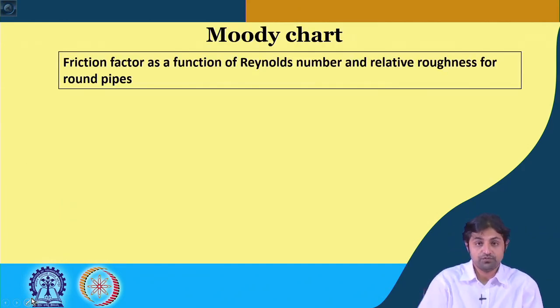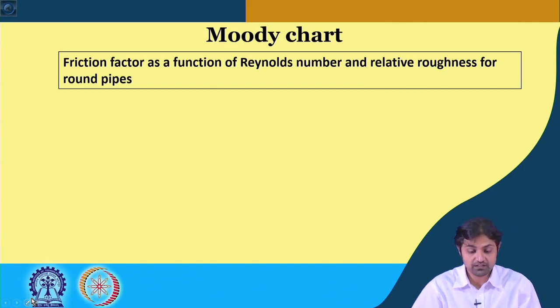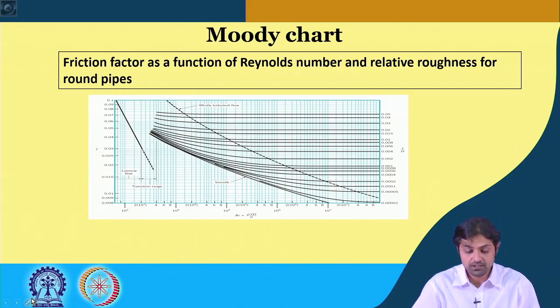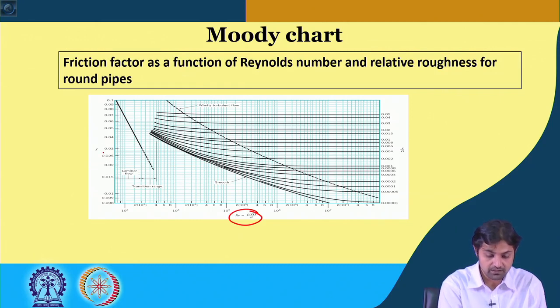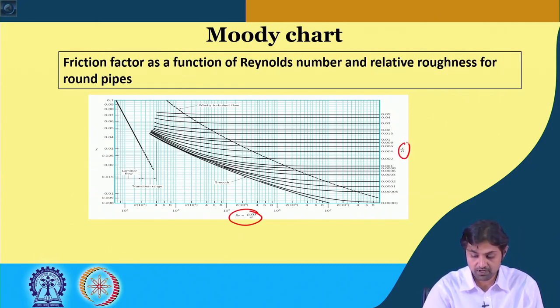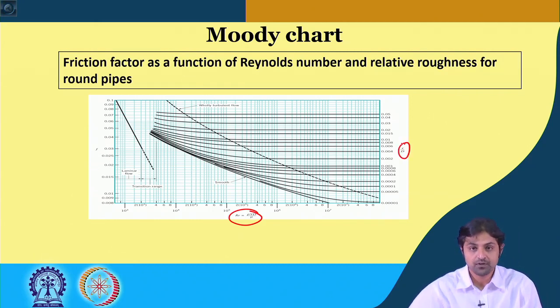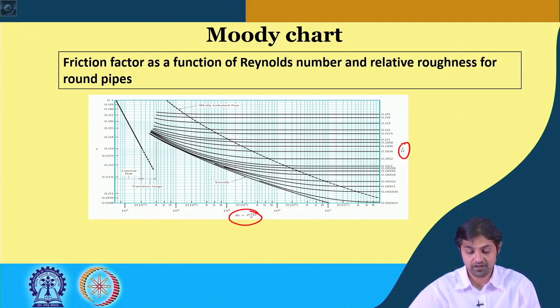To find the friction factor, there is something called a Moody chart. Friction factor is a function of Reynolds number and relative roughness for round pipes — it is a chart where Reynolds number is on the x-axis, F is read off the y-axis, and ε/D is plotted on the right. This is the oldest method of finding the Darcy friction factor.